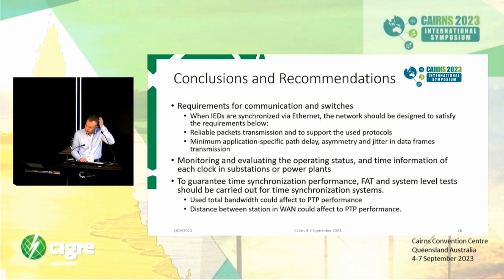So you mean you can simulate the E1 channel for protection, using packet-based wide area communication? Yeah, packet-based communication can be used for that, and the protection can use this simulated, or emulated, E1 for protection. That's possible using the ping pong algorithm, emulating E1 over the packet switch network, but in that case timing is needed for the circuit emulation.